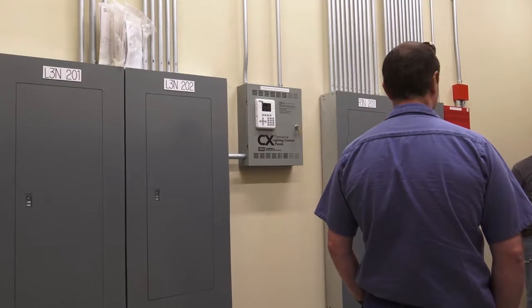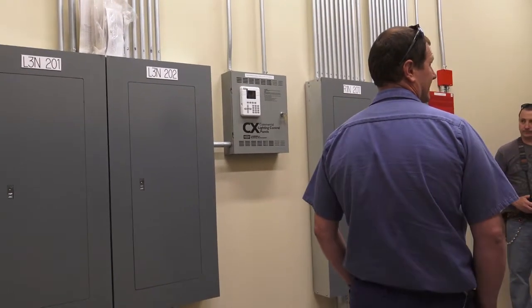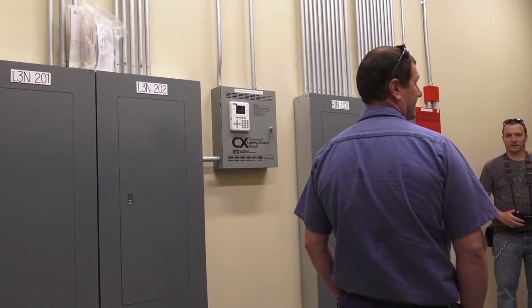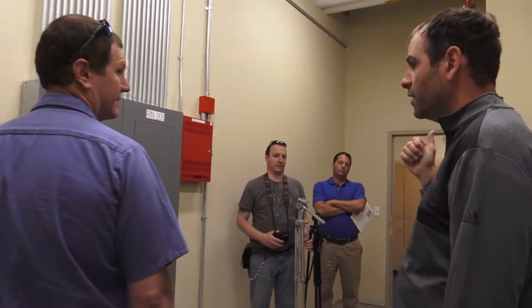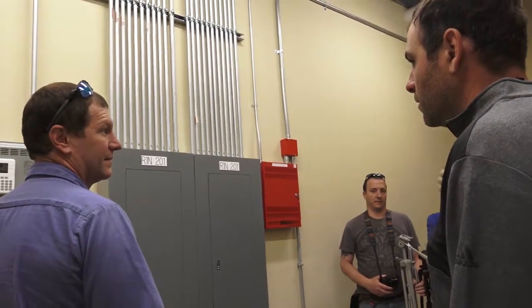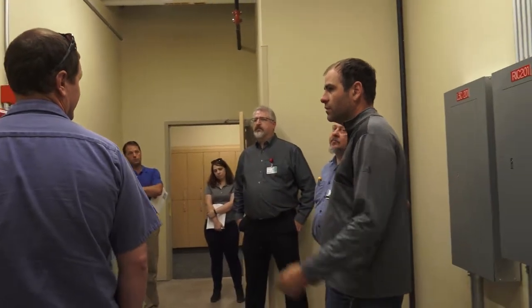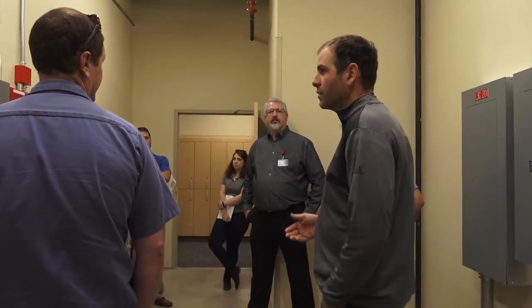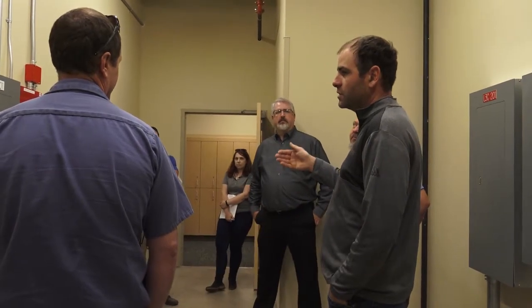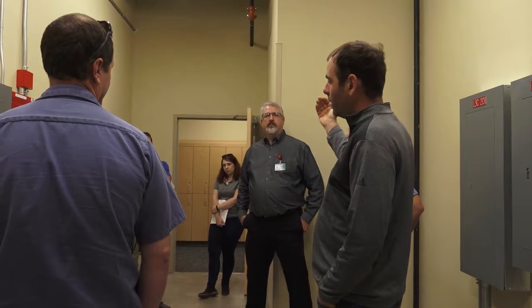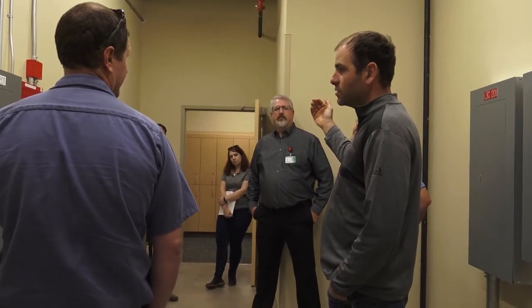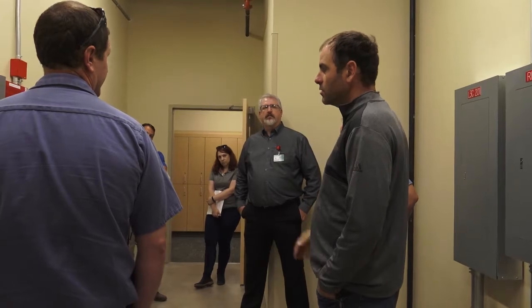So the lighting control, this one is basically just, for the most part, it's got the life safety circuits in the hallway. The life safety lights are on there, and then if there's a power failure, they switch over to normal or emergency on. So if we lose normal power in the hallways, the lights come on. Right now it's programmed from, I can't remember what time, to 6 o'clock, and then it shuts off. But in the hallway there are also occupancy sensors powering the normal power lights, so if those normal power lights shut off, it clicks emergency stuff on if the relay happens to be off.